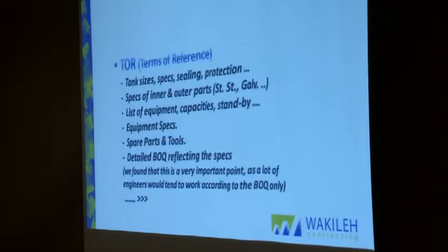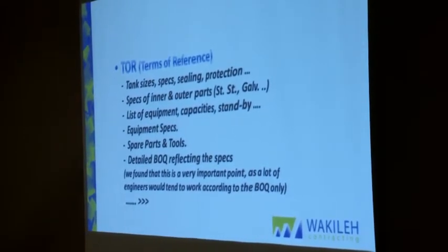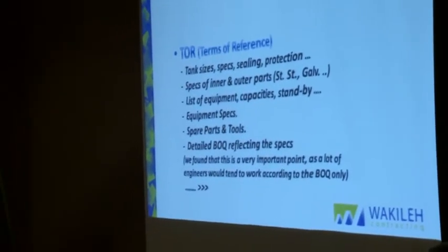We have to list the equipment, as I said before, put the right specifications, be more specific on the specifications. And then, in many cases, many of the specifications we have seen included the spare parts. The spare parts are not inserted in the BOQ, and then they are forgotten. It's always good to put that the BOQ will contain a summary of my specifications. Then you don't miss items, expensive items like spare parts.